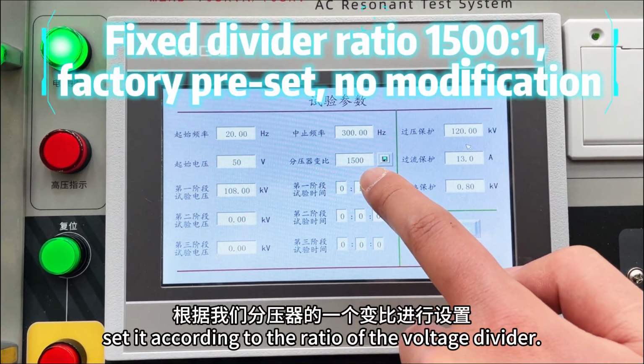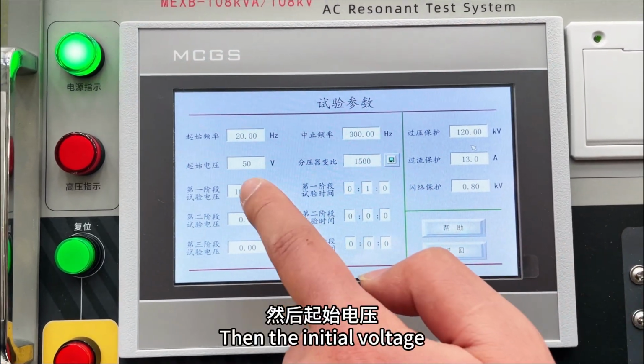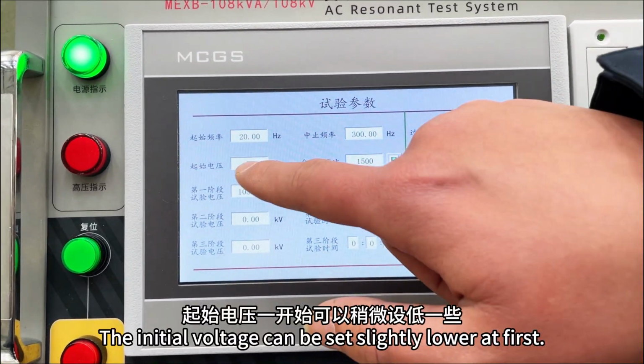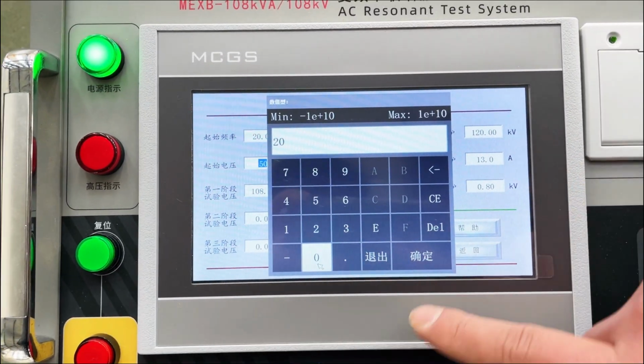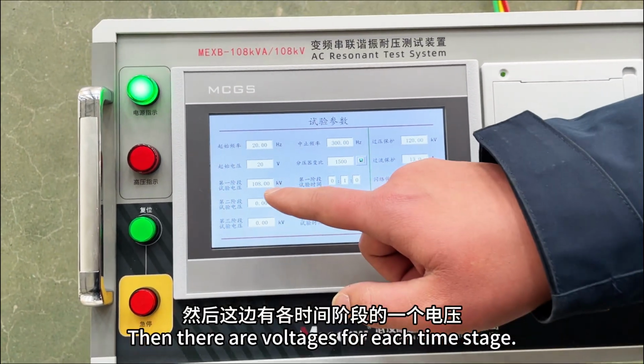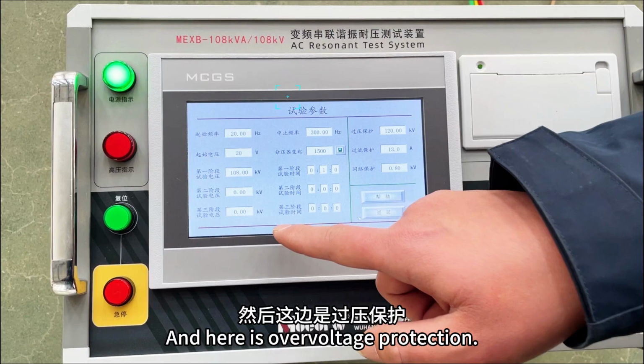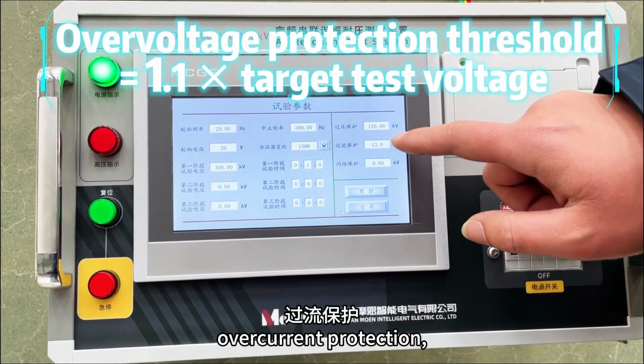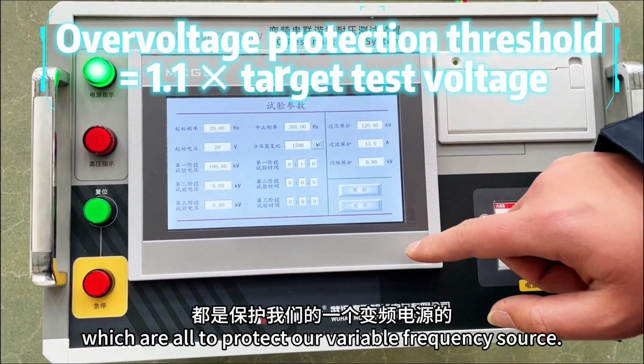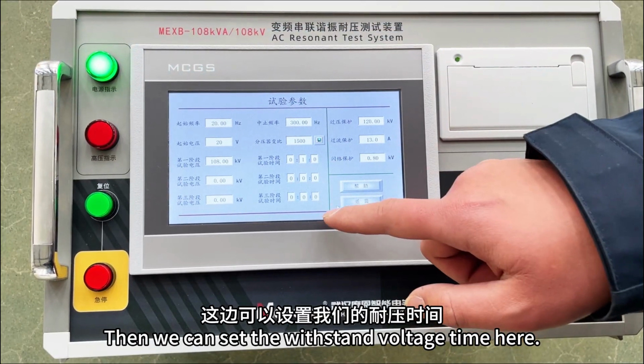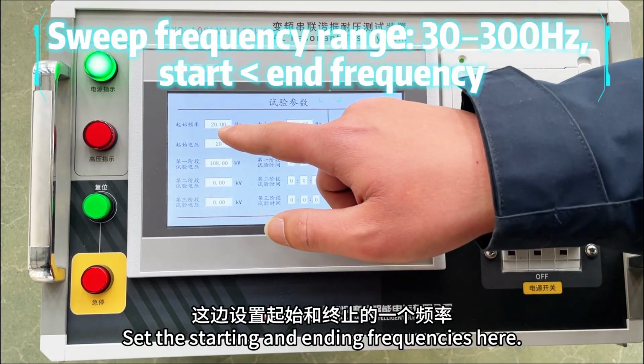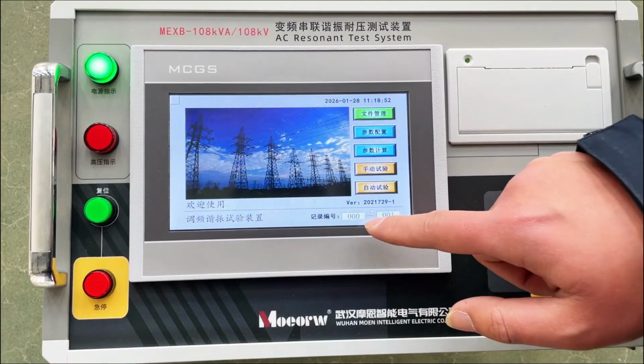Set it according to the ratio of the voltage divider, then the initial voltage. The initial voltage can be set slightly lower at first. Then there are voltages for each time stage. And here is overvoltage protection, overcurrent protection, which are all to protect our variable frequency source. Then we can set the withstand voltage time here. Set the starting and ending frequencies here.